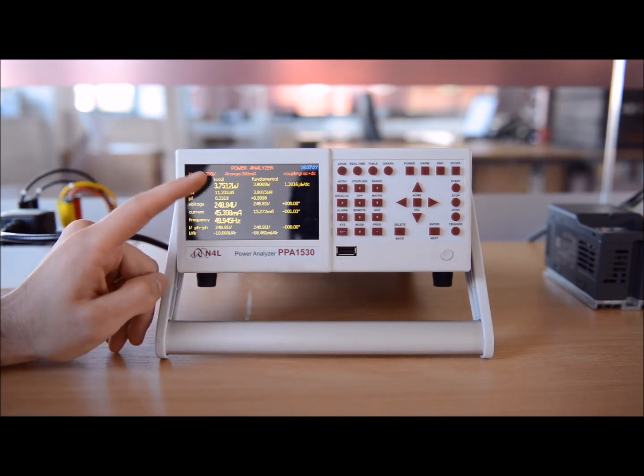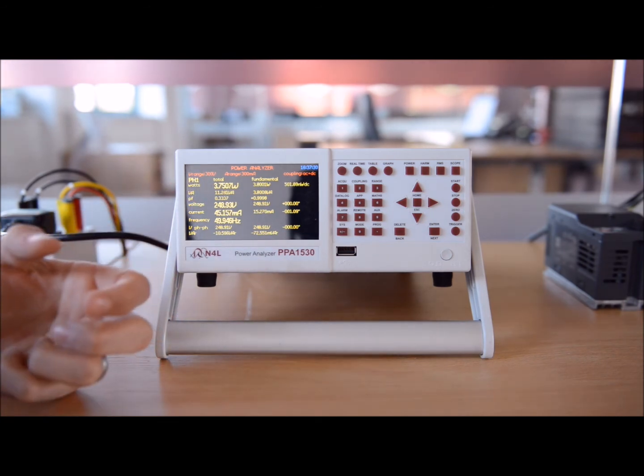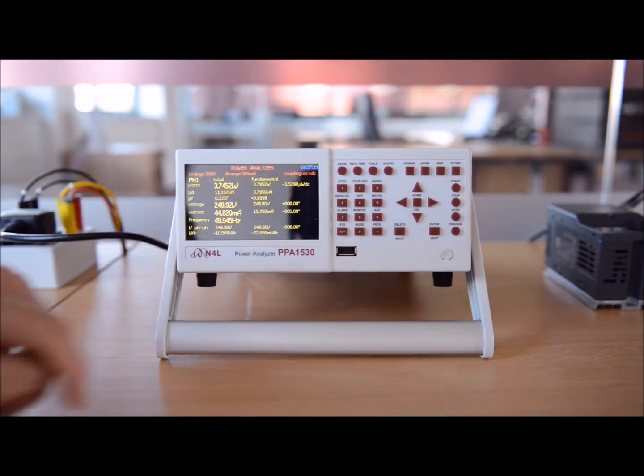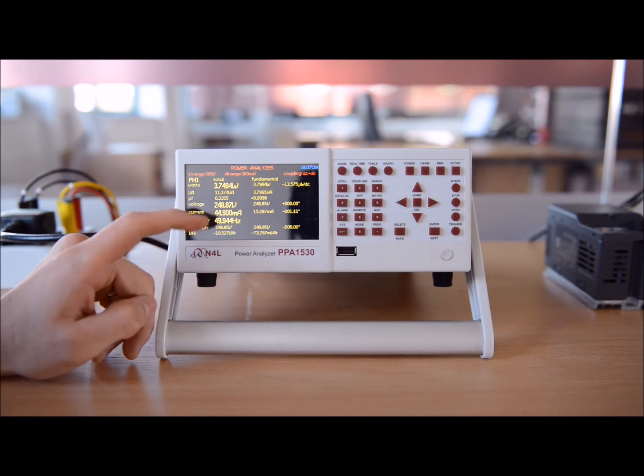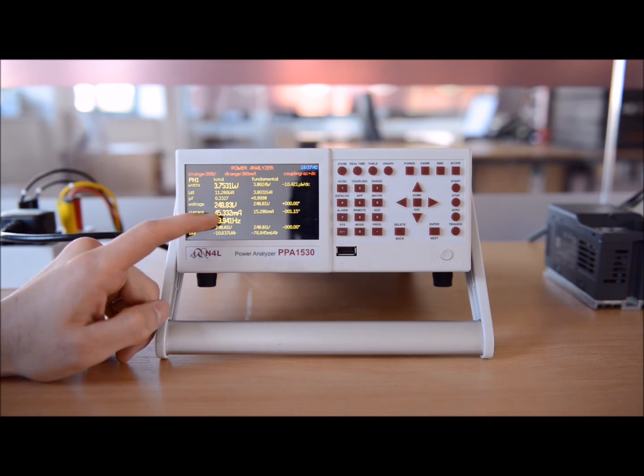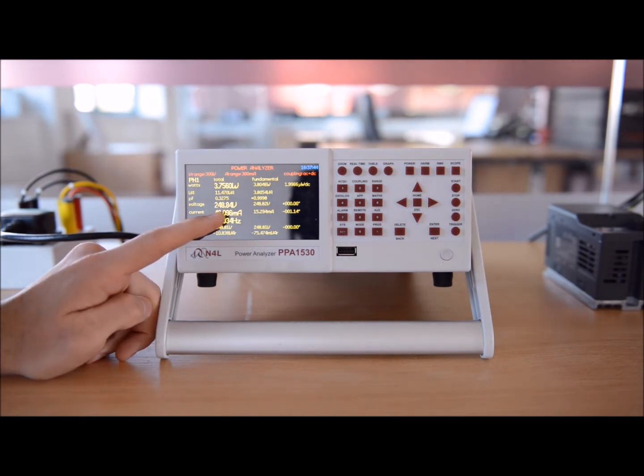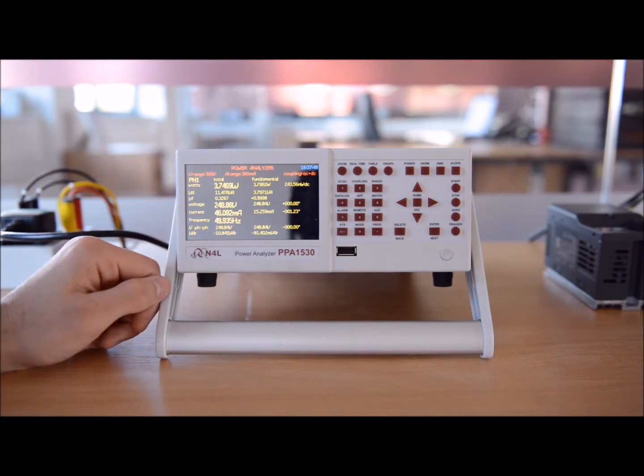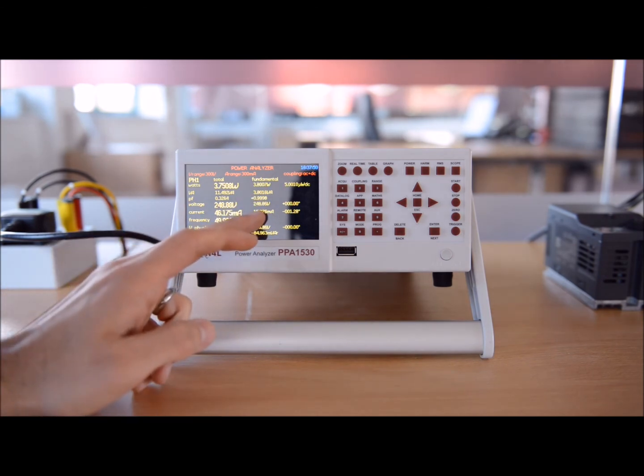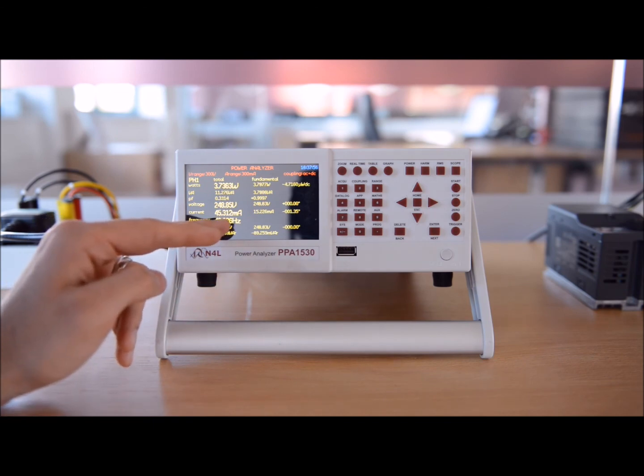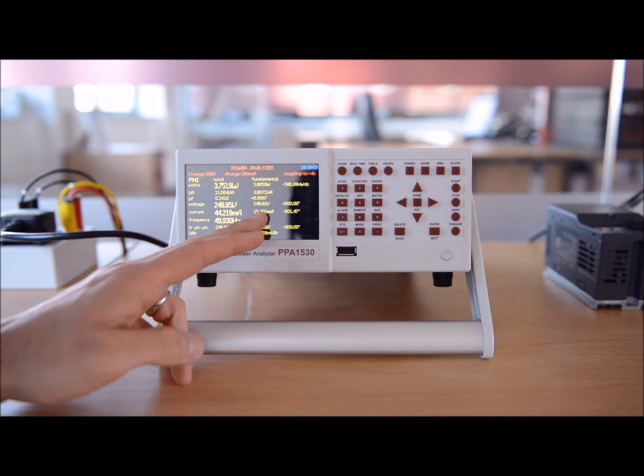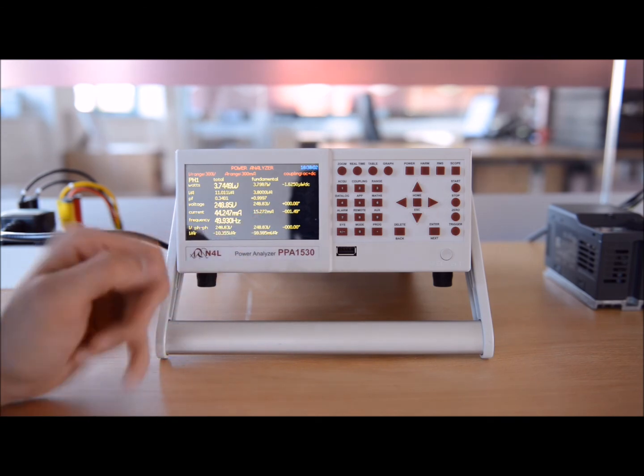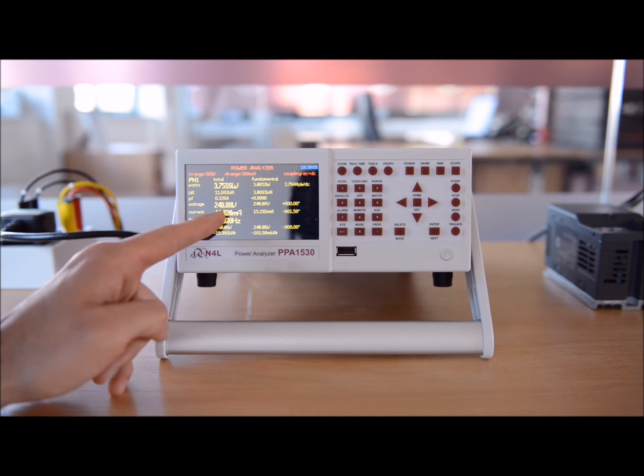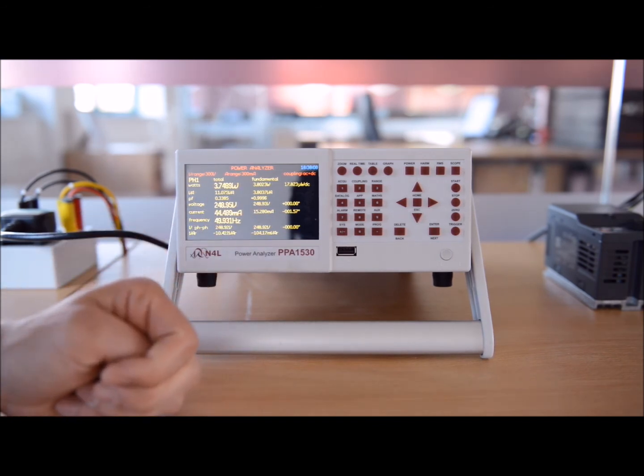Now of course what we've got here is, due to the fact we perform a real-time DFT, total and fundamental separated, real-time, live during the measurement. What that means we can achieve is we can separate the total wideband RMS signal, so we've got 46.0 or 46.1 milliamps wideband, and then we've got 15 milliamps fundamental. So what that means is the 50 Hz or the 49.936 Hz component of that distorted current waveform is 15 milliamps, whereas the wideband RMS is 44 milliamps. So there's a big difference, hence the large distortion.